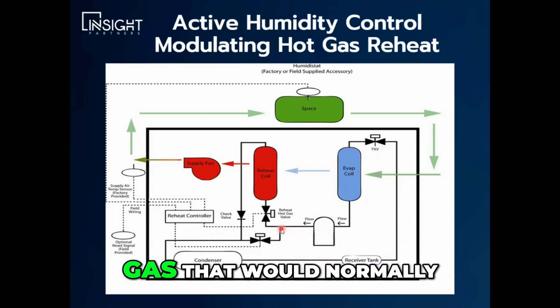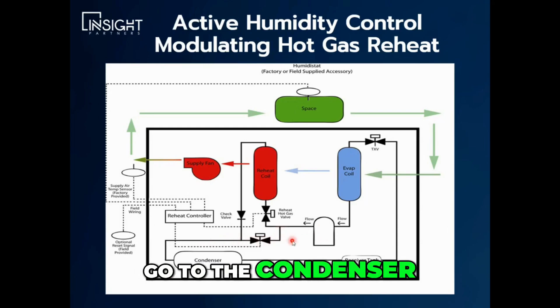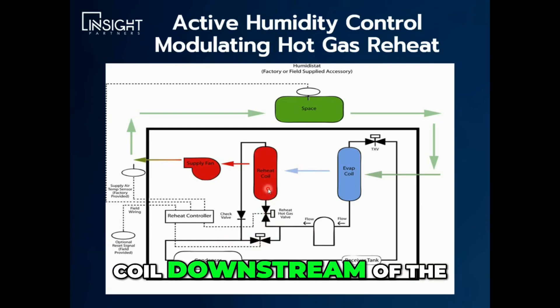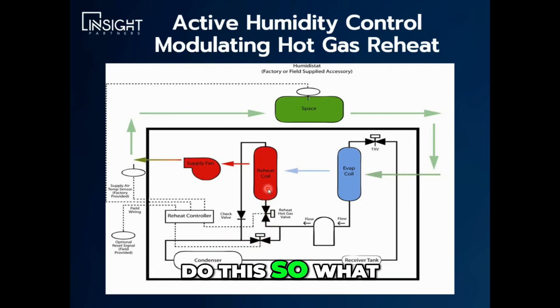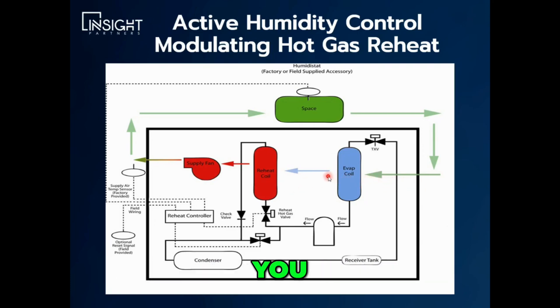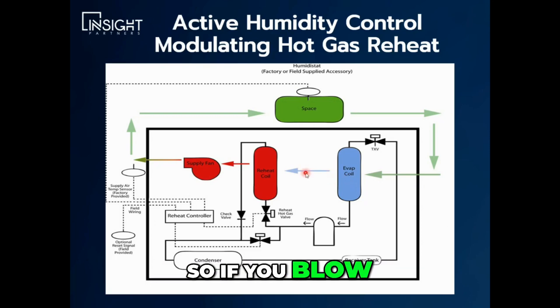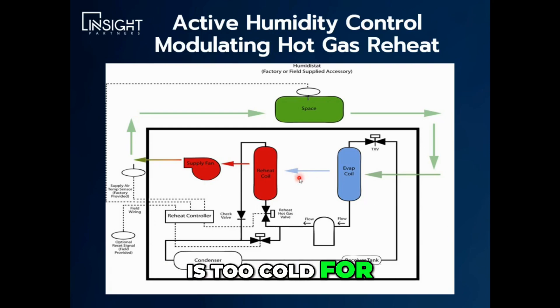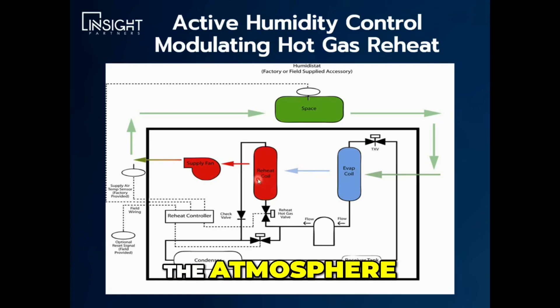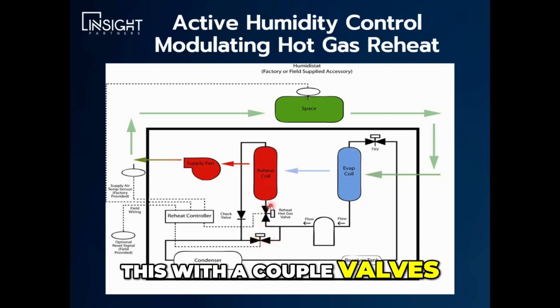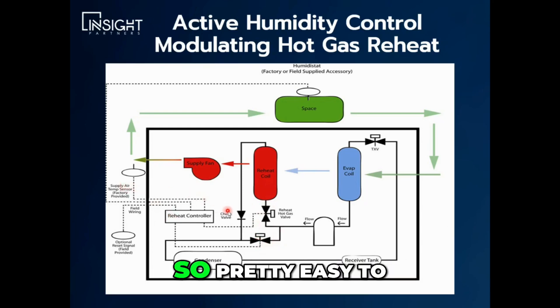What happens in a reheat system is we take some of the gas that would normally go to the condenser and we divert it over to the reheat coil. The reheat coil is generally a one or two row coil downstream of the evaporator coil. Why would you do this? Mostly in a dehumidification cycle, you're taking the air across the evaporator coil and removing the moisture from it. You're generally leaving the coil in the low 50s. So if you blow very cold air into your space and it's hot outside, that's great. But sometimes at low conditions, that air is too cold for the space. So we reheat the air with this reheat coil, using the heat that would generally go to the atmosphere. And we can accomplish this with a couple valves, a reheat controller, and a couple sensors. So it's pretty easy to do today, very common.